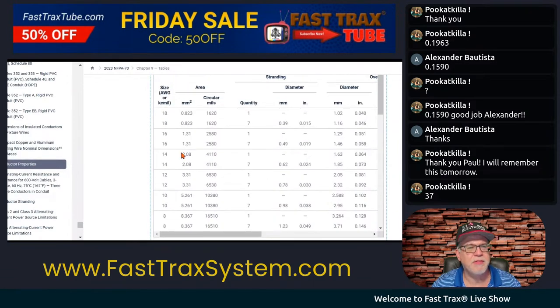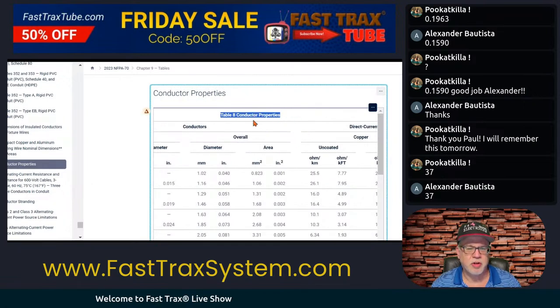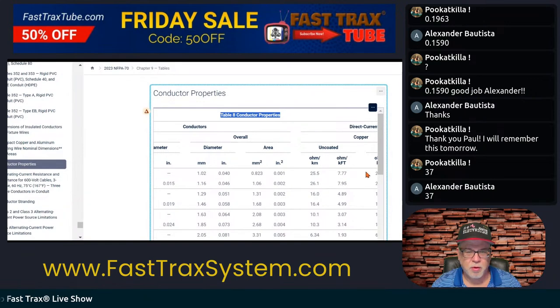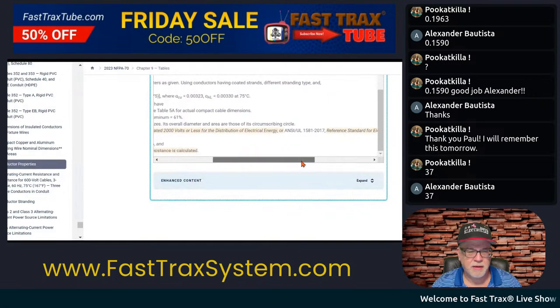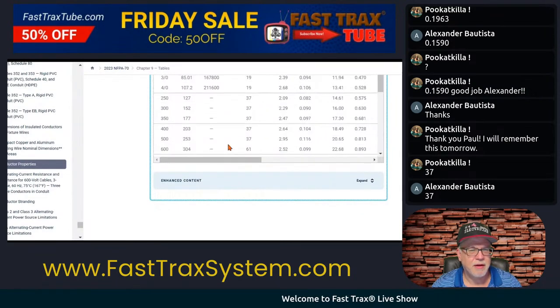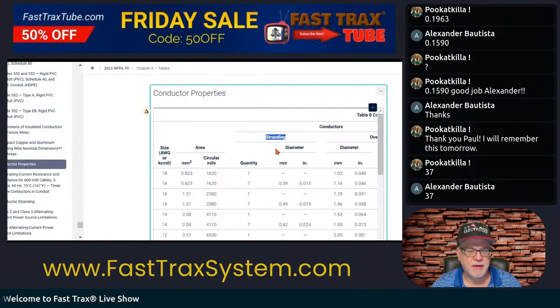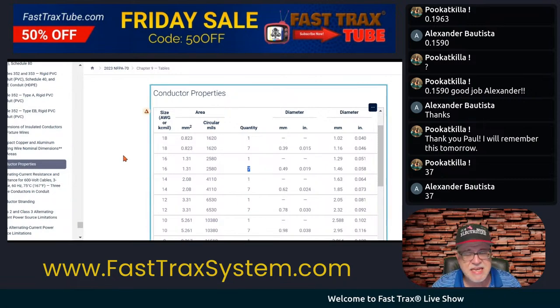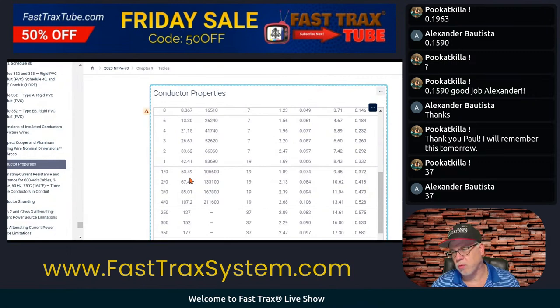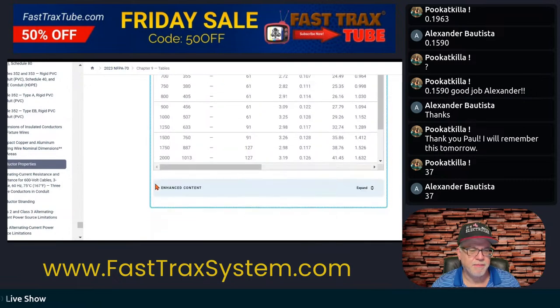Let's go to conductor properties. Right here — Table 8, conductor properties. So what we're going to do is go down and look. You notice there is quantity — quantity of stranding. One represents solid conductors. Seven represents stranding — this is normal, typical ASTM Class B stranding. Our question was for 400 kcmil right here. So typical — that's a 37-strand. Class B stranding is listed as well as solid for some sizes. That is typically the normal building wire that the NEC deals with.